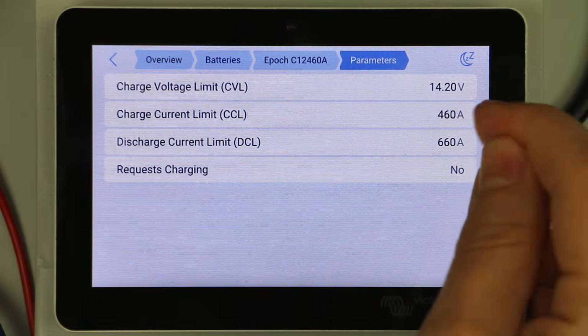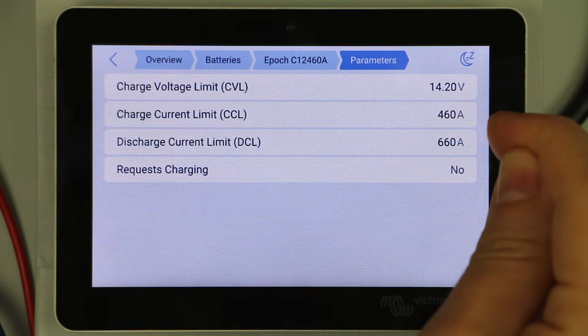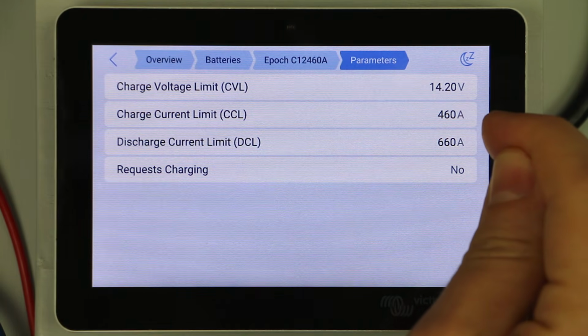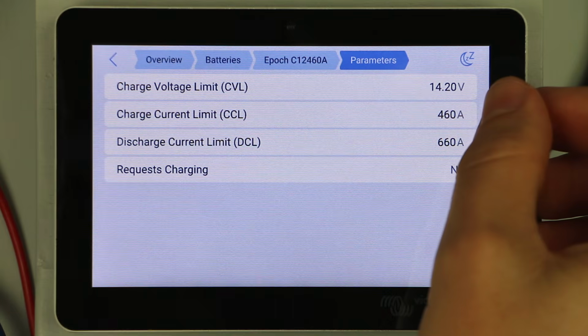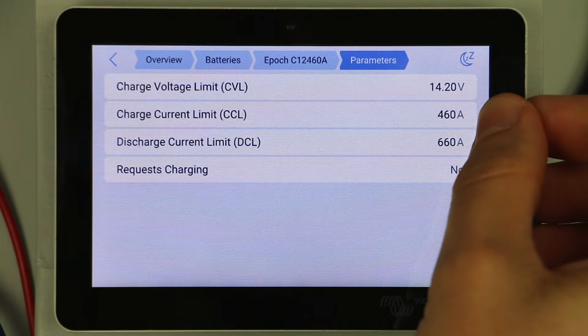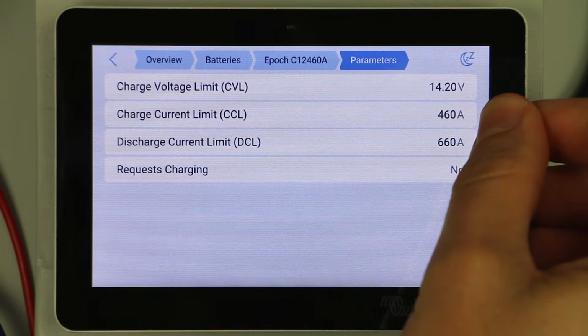Basically the charge current limit is going to be passed to DVCC, and it's going to tell the chargers, hey, we can no longer send 460 amps to the battery bank. We need to drop that down to 230 amps, and it will throttle the chargers if needed to that new lower limit. So that is definitely very handy and great for the batteries.